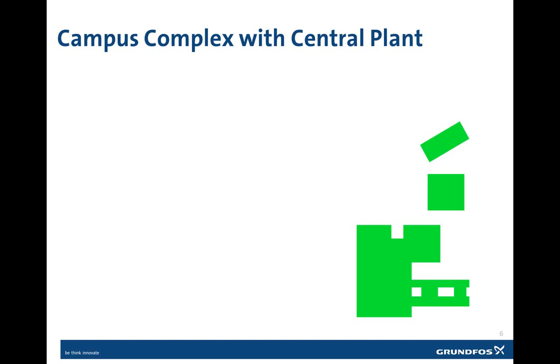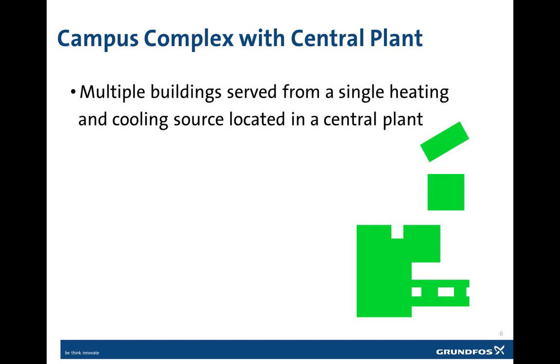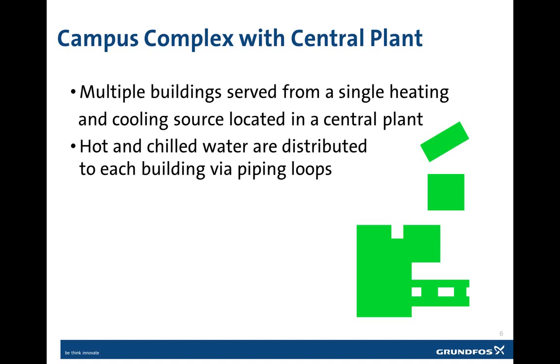Now, when there are multiple buildings, such as a large complex with a central plant, the multiple buildings are served from a single heating and cooling source located in the central plant. The hot and chilled water are both distributed to each of the buildings through piping loops. Ideally, the central plant should be central to all the buildings, but that rarely happens. Often the architectural design wouldn't allow it. The farther the chiller plant is from the most distant building, the more expensive it is to both build and operate the heating and cooling system for the plant.